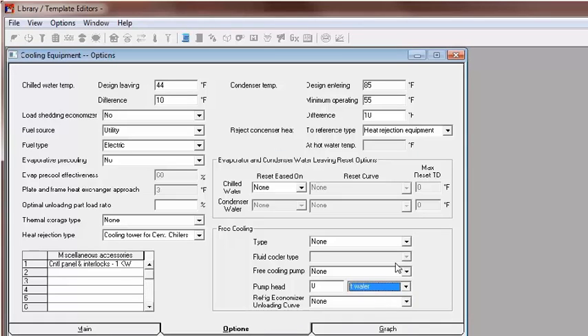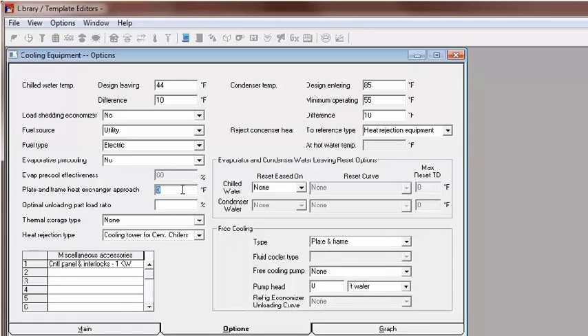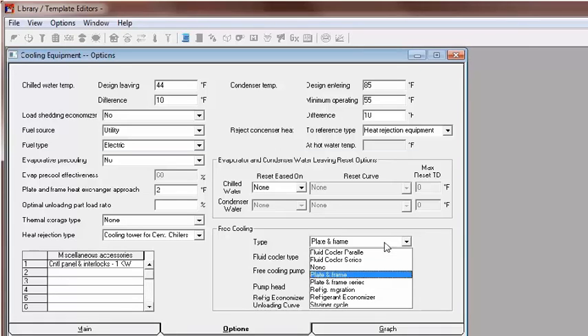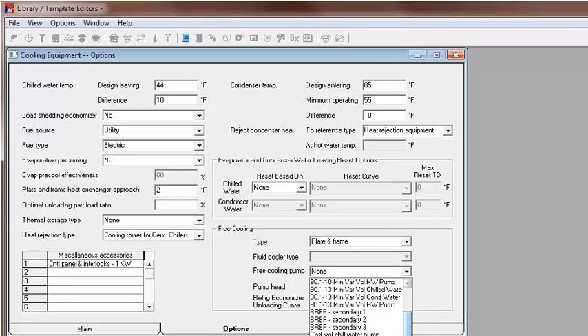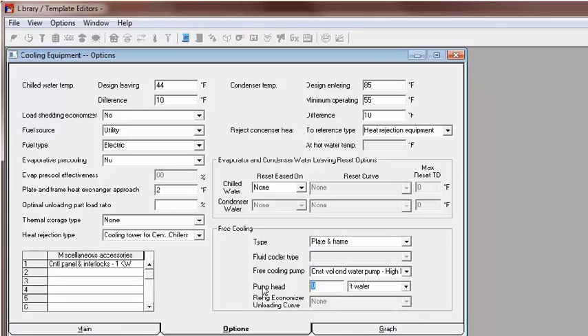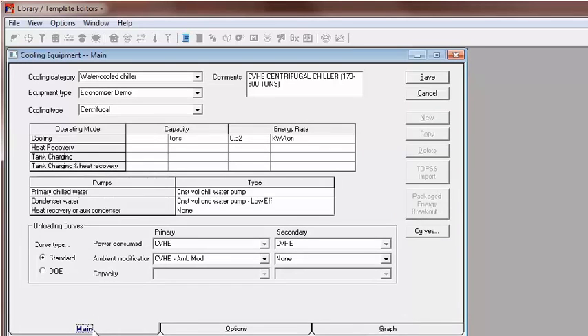Once the free cooling type has been changed from None, the plate and frame heat exchanger approach field is no longer read-only. The default value for the heat exchanger approach in TRACE 700 is 3°F. Strainer Cycle does not use the plate and frame heat exchanger approach field. For either parallel or series heat exchangers, you select the pump and its full load energy rate here. No pump is required for strainer or refrigerant migration. I'll create a parallel-configured plate and frame heat exchanger with the high efficiency constant volume condenser pump at 30 feet. Then back at the main tab, I'll save this new chiller with its free cooling already built right in.